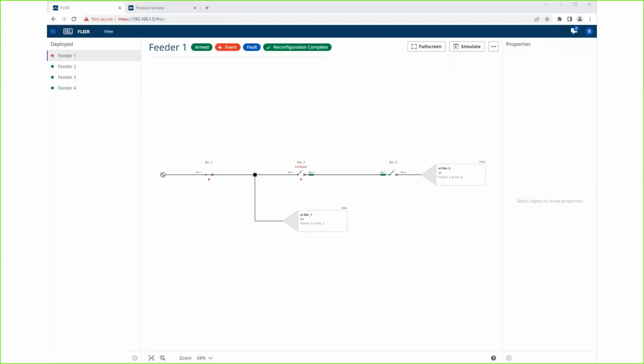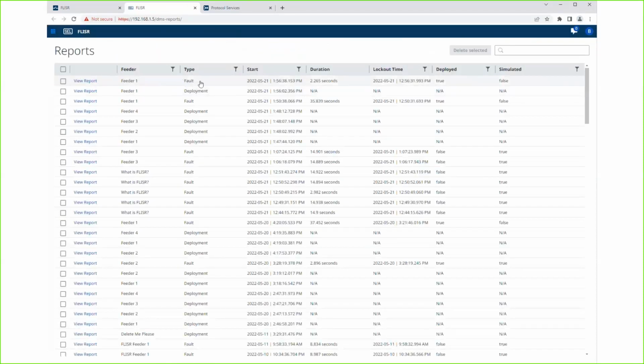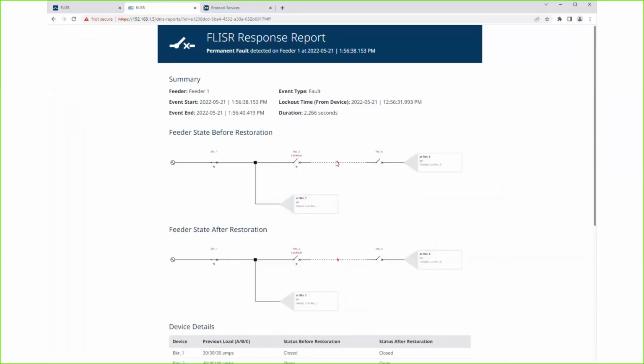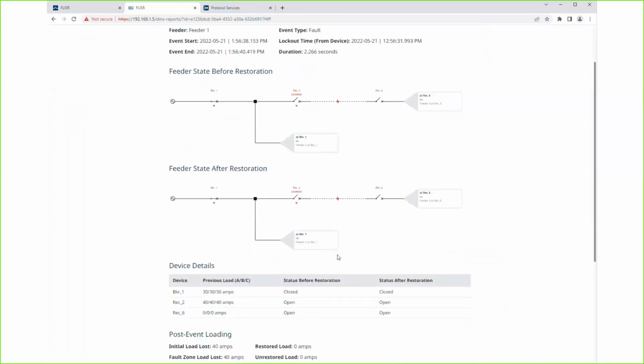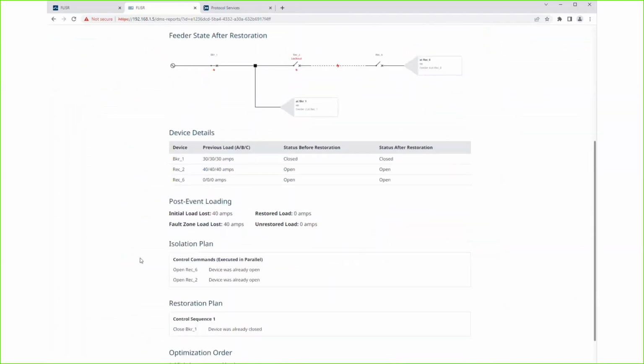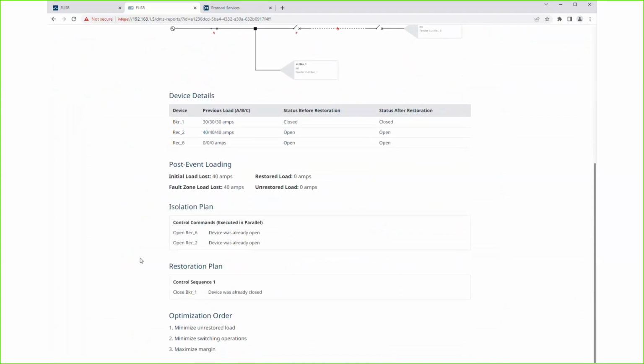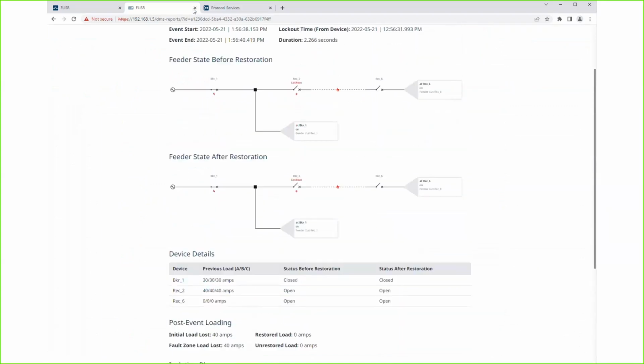So there's that fault again, downline of Recloser 2, and almost immediately reconfiguration is complete because there's nothing FLISR can do here. There is no Rec 4 to open. And you can see I get a report for each one of these. This is very short because there's nothing we could do, but we did recognize that there's a fault downline of Recloser 2, and there was no action we could have taken. So it generates a report, and it tells you what it checked, but no action was taken in this case.